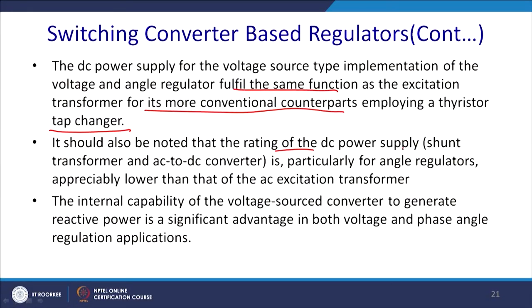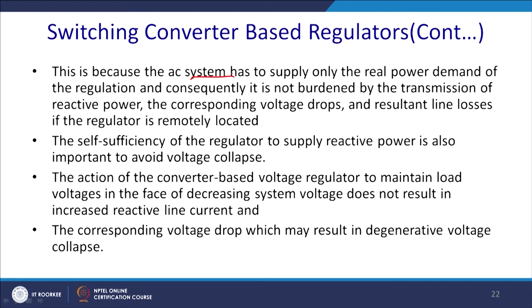It should be noted that the rating of the DC power supply and the shunt AC to DC converter of angle regulators is appreciably lower than that of the AC excitation transformer. The internal capability of the voltage source converter to generate reactive power is a significant advantage of both voltage and phase angle applications. This is because the system has to supply only the real power demand of the regulation, and consequently it is not burdened by the transmission of reactive power. The corresponding voltage drop would otherwise result in line loss if the regulator is remotely located. This is actually one of the drawbacks.